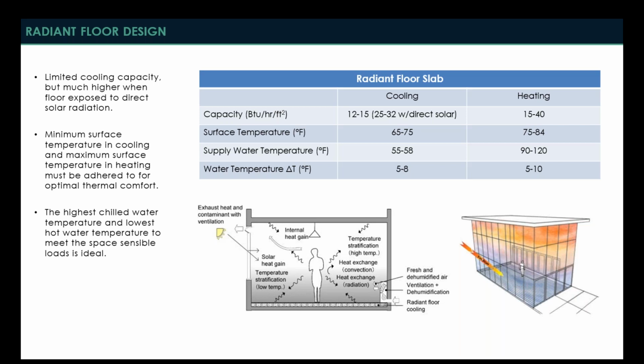And these are four of the very important factors that need to be taken into consideration when you're looking at these radiant systems. There's many more beyond this, but I think for a high-level discussion of understanding how these work, these four are maybe the most important. So when you look at the capacity on the cooling side for a radiant floor slab, having a typical capacity of 12 to 15 BTUs per hour per square foot is quite low in comparison to all air systems.